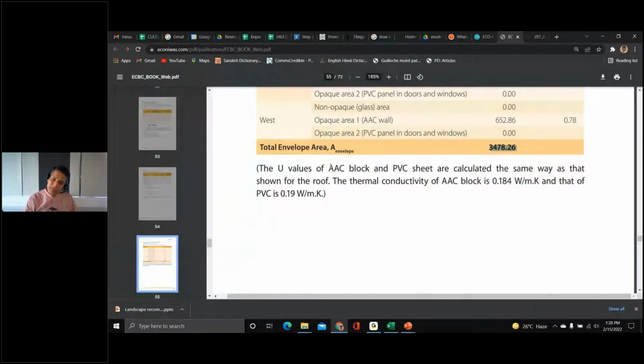The U value of AAC block and PVC sheet are calculated the same way as shown for the roof. The thermal conductivity of AAC is 0.184 watt per meter Kelvin and that of PVC is 0.19. Now where did this conductivity value come from? If you open the National Building Code or SP 41 1987, they give you U values, but they also have material property tables. If you want to calculate U value yourself, you need specific heat capacity, density, and conductivity - these three values. In engineering, all of you would have done it, maybe in architecture too, but actually we've done this in 9th class physics in school. If you have these three values, you can calculate the U values. So they've mentioned the conductivity value of AAC block, which is readily available in your Indian national codes.